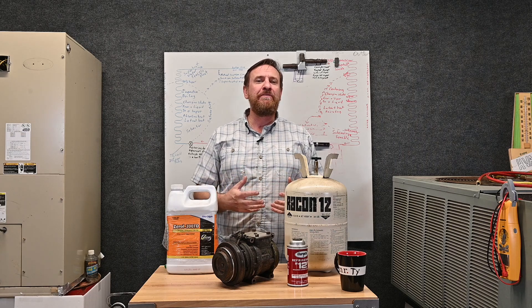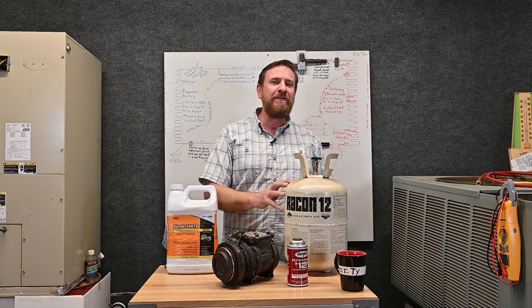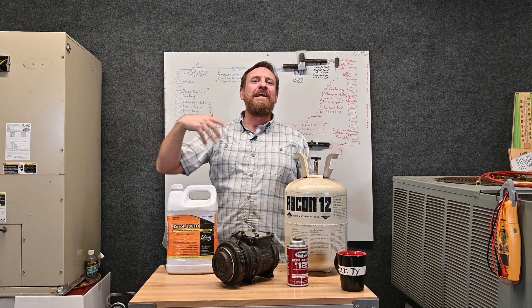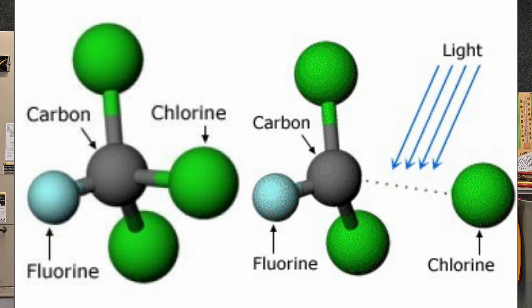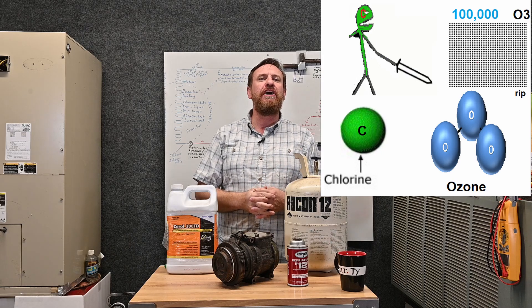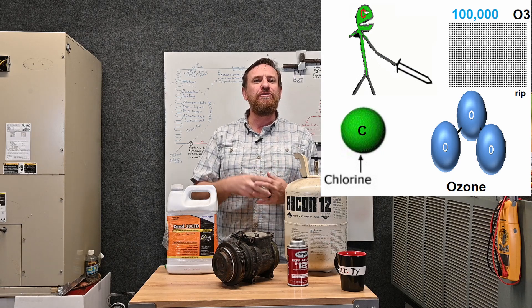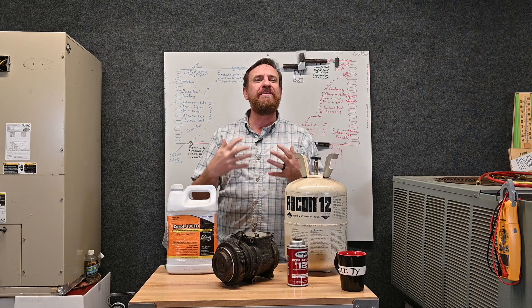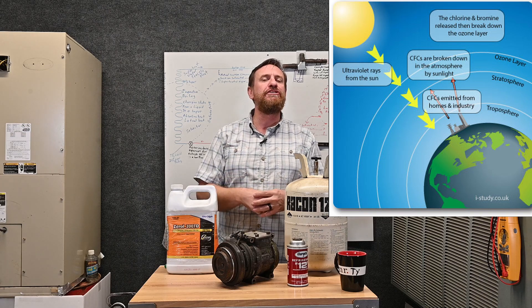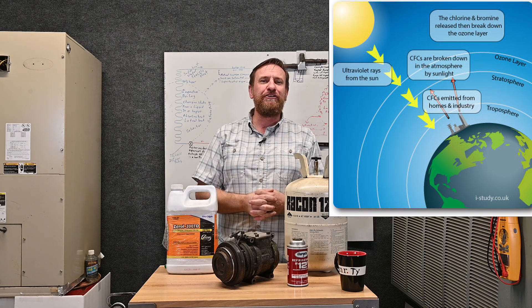R12 was a great refrigerant — it was a single molecule refrigerant. The problem is they found out that this refrigerant would leak out, or people would vent it, and it would end up in the atmosphere. When it ended up in the atmosphere, UV rays from the sun would break the refrigerant down. Because of the CFC, it broke apart very easily, and that chlorine molecule would be free. One molecule of chlorine destroys 100,000 molecules of ozone — and that is an EPA test question. One molecule of chlorine is going to destroy 100,000 molecules of ozone.